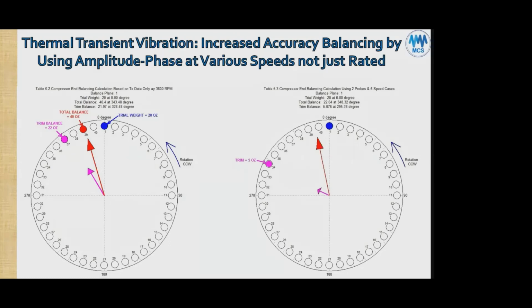However, it's because they used data which are not at steady state. They were more at 3,600 RPM, but not capturing the different loads at different speeds. So if they had operated with various loads, like 0 load, 25% load, 50% load and 100% load at 3,600 RPM, and then made calculations based upon each load, and hopefully tried to average. If they notice that the machine is reversible, as you went to 100% load, then you brought it back down to 25%, and you found it was reversible, then it means you're going to be stuck with this variation always.